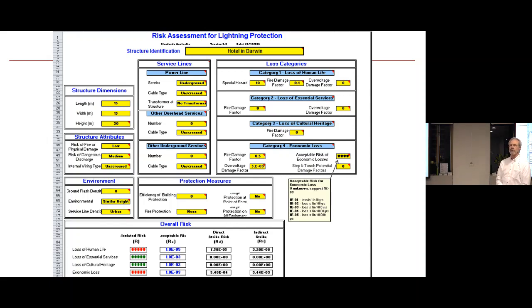Another one, which often we don't have any figure entered in for, is loss of cultural heritage. But if the structure does have cultural heritage, it can significantly affect the outcome of the calculation. And the economic loss, that's a bit of a funny one. They have an acceptable risk of economic loss. It says if unknown, enter in a particular value there. And I think a lot of people don't really know what to put there, so I'll leave it at that. You also enter in the fire-related damage factor. Fire is a significant risk from lightning damage, because lightning can cause arcing and set your structure alight.